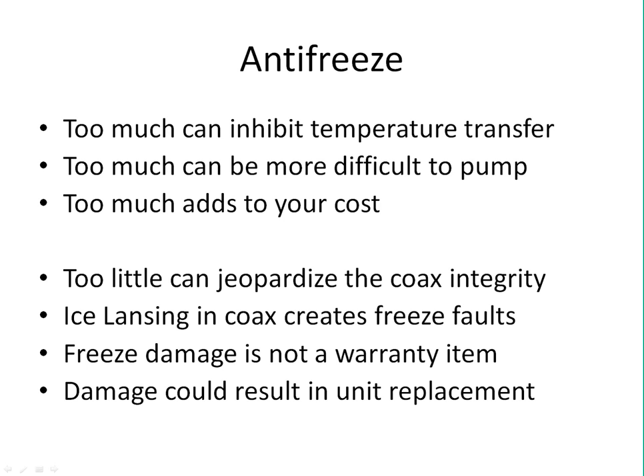Antifreeze, one of the things that I've seen in my career is I go out to projects and a lot of guys have done the antifreeze additive by gosh and by golly. In other words, they just kind of threw some in there, didn't really calculate, and over-antifreezing is more common than what I've seen. You can typically see it and smell it when you draw a sample. And that's not good either, because too much antifreeze can inhibit your temperature transfer.